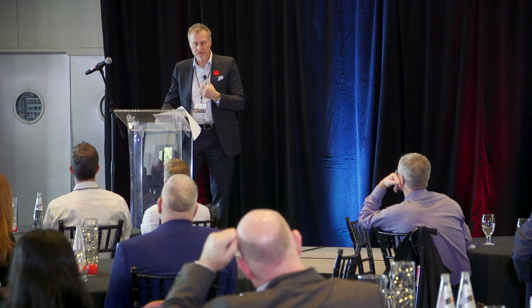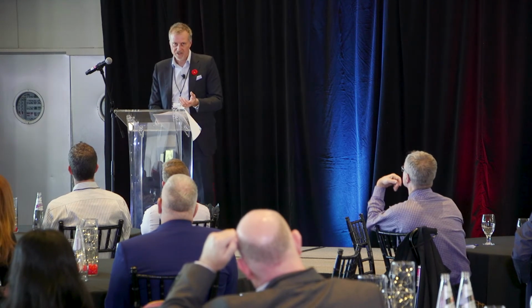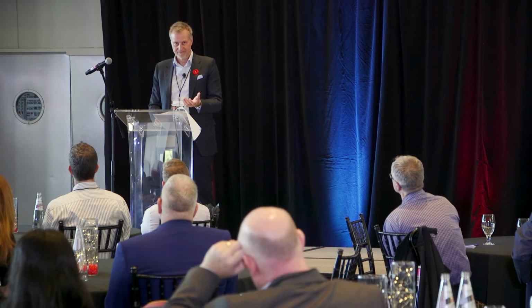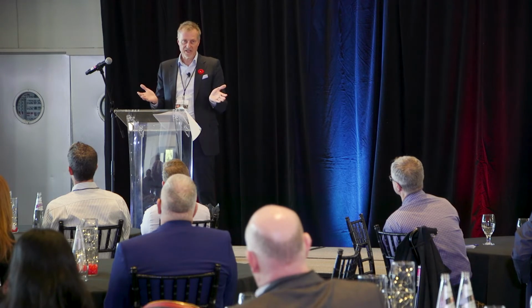In our industry, what do we have at the end of the shaft? An impeller. And that impeller is creating pressure to move water through the system. As valves open or close, the pressure required either increases or decreases, and the amount of work the motor is doing is either going to increase or decrease. It varies the torque, varies the load. That's the affinity laws.